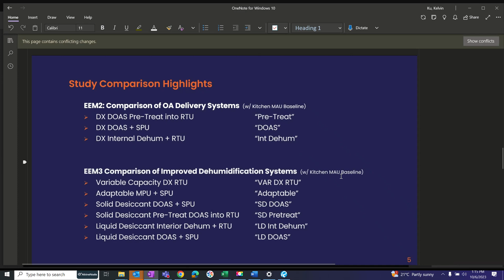No. So the baseline is the kitchen pretty much taking care of itself with makeup air units. However, a deficit or a negative pressure of 10%. So the sales floor units, that in this case would be our unit, and as needed, some single path recirculation units, because sometimes you need those accessory units, right? We would provide that missing air as what we call transfer air. So essentially, whatever that CFM, that 10% equates to, we bring in that additional outside air.